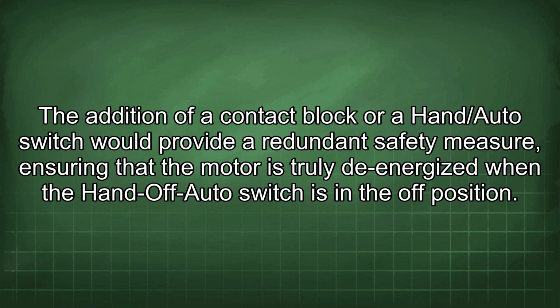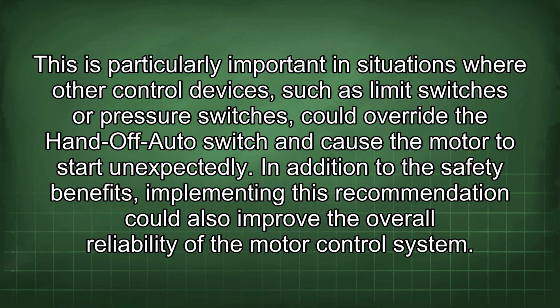The addition of a contact block or a hand/auto switch would provide a redundant safety measure, ensuring that the motor is truly de-energized when the hand-off-auto switch is in the off position. This is particularly important in situations where other control devices, such as limit switches or pressure switches, could override the hand-off-auto switch and cause the motor to start unexpectedly.